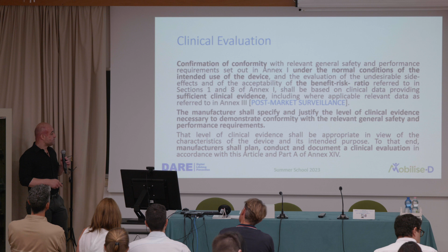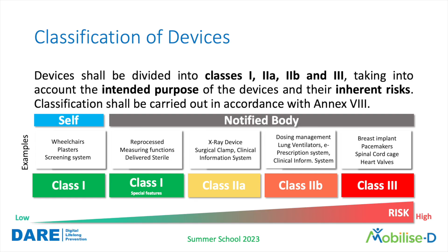On the basis of the specific application in Europe, but it's the same also in the US, just with different terminology and categorization, according to how high the risk is for the application, you have different classes of medical devices. A pair of crutches is a class 1 medical device, so the risk is very low. If you have a device that in the intended purpose has a measurement, like measuring blood pressure, it is not putting anyone at risk, as putting on the device to measure blood pressure is not harming anyone, but still you are stating that it's a measurement. In that case, it's a bit more than a class 1, and it's certified by a notified body already.